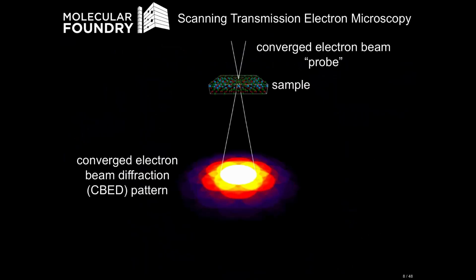And then you place your sample at the crossover point where you have the smallest possible electron probe. For a modern aberration-corrected STEM instrument, we can get down to about half an angstrom size of probe, small enough to probe atomic resolution for most samples.